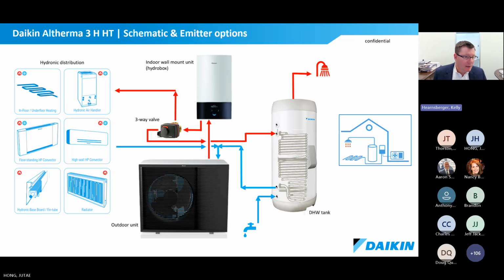It would replace the familiar radiator in a new build home, and it provides the comfort that you would have received from the radiator before, but now it's utilizing a small micro fan coil. So you're getting very good heat and cool output, but you're only using a very small amount of energy. And that's why you can heat at 140 degrees through these convectors, just like the high wall, which is buddied to the right-hand side there. They show the symbols of heating and cooling, so those are capable of heating and cooling.